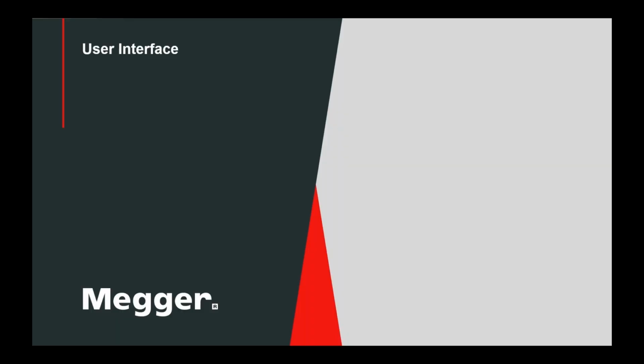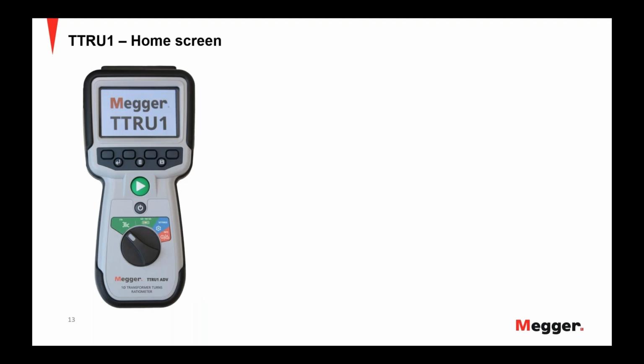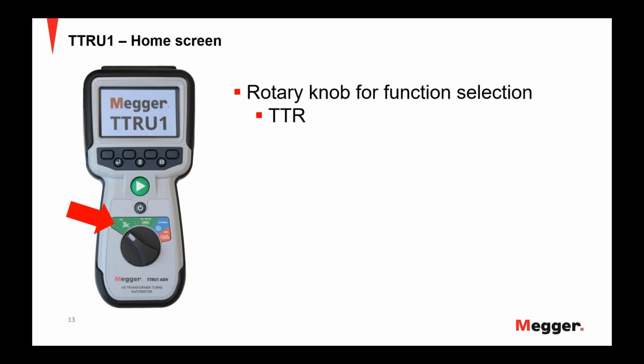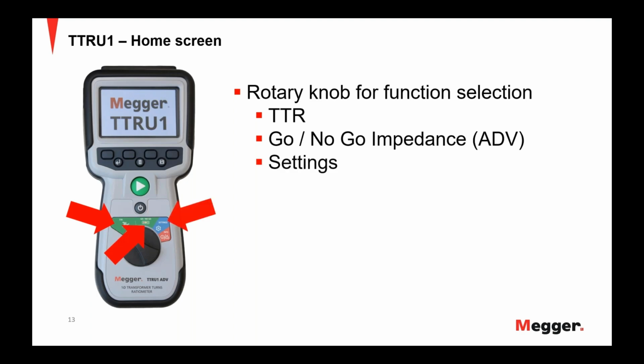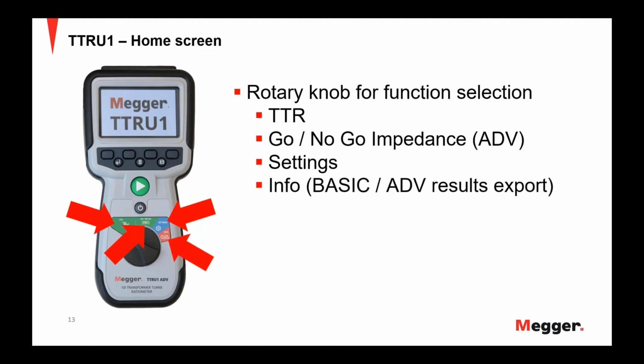Now looking at the user interface of the TTRU1, it's a very simple device with a rotary knob for the different function selection. So as you go from left to right on the device, you start with your typical turns ratio test, your TTR. You will then have the go, no go test in the advanced model, and then some settings. So, your date and time configuration, the maximum voltage that you want to inject, things like that. And then finally, you have the information screen. And for the basic and the advanced model, this is how you are going to export those results.